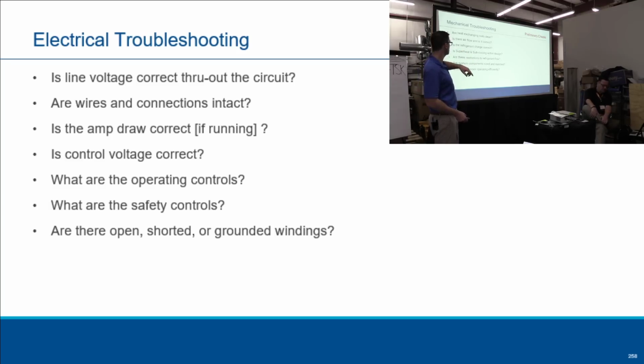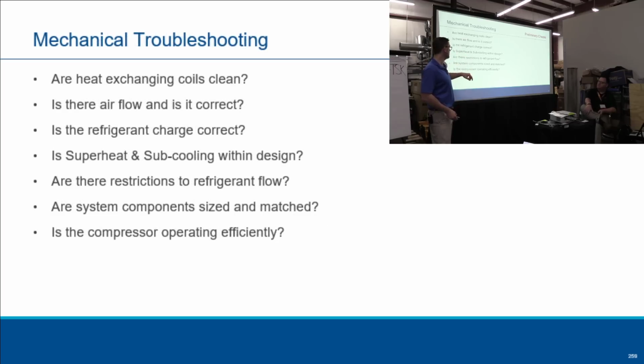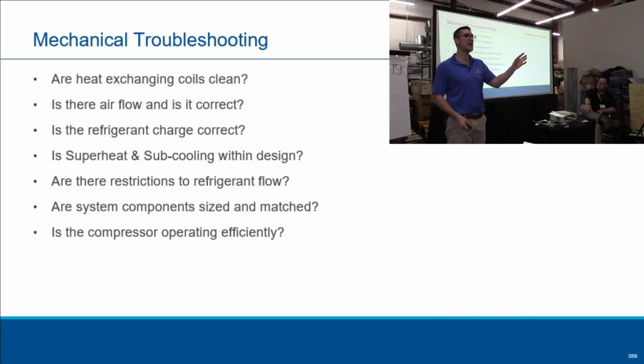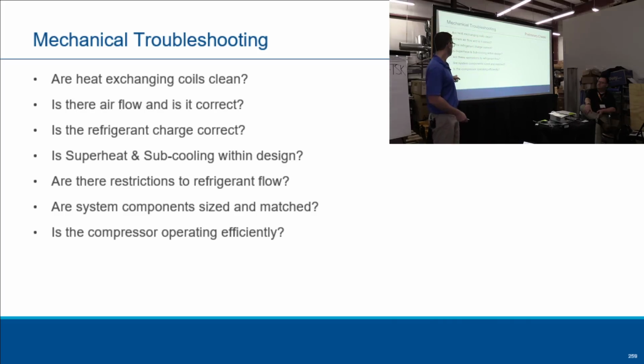Is the refrigerant charge correct? Superheat, subcool, is it within design? Are there restrictions? Is the component sized properly? I get this a lot. A guy comes in, changes a part like for like, and goes back out. Well, that part was the wrong part that somebody else installed, and that's why you got another failed compressor. Right? Is the compressor operating efficiently?